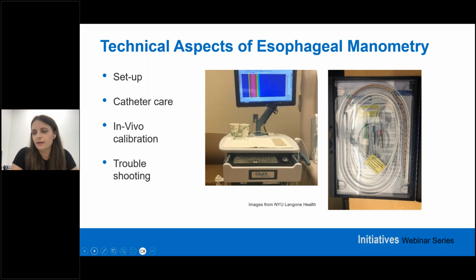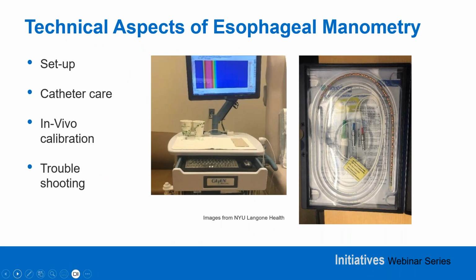Our clinic always used the Medtronic ManoScan software and the Medtronic esophageal manometry catheters. I can't speak to other software from other companies, but the Medtronic software very seamlessly guides you through calibrating the catheter prior to placement, making sure all the sensors are functioning properly before we put the catheter in, just in case there are indeed any structural problems with the catheter that could cause an inaccurate reading during the study.